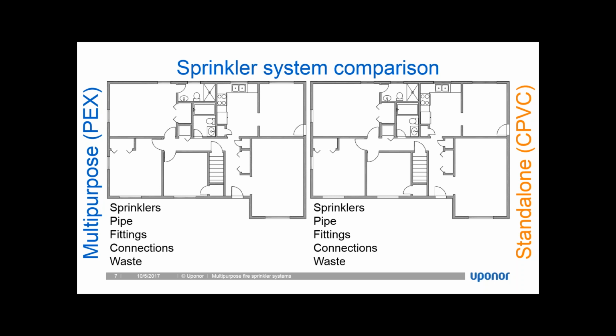All right, so what we'll look at is how sprinklers lay out in these two buildings. Here we're looking at the upper level. It's going to be pretty much the same because the rules don't change depending on what material you're using from a standards standpoint. Another thing that we're not going to look at is pipe sizes, which aren't accounted for in this comparison. The plumbing comparisons that we do are going to use the same material, because you would normally install, or at least that's the way it's trending, PEX for the residential domestic water application, but the systems will look different because we're going to have a standalone plumbing application and a multi-purpose plumbing application. I'm also not going to include the pipes for the connections between levels because that's just a little bit redundant, and I was maybe a little bit lazy too.